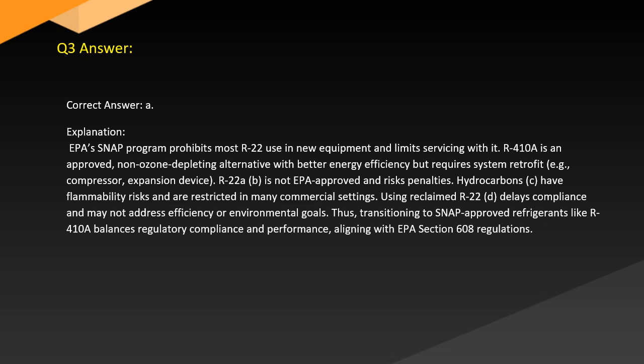Answer. Correct answer: A. Explanation. The EPA SNAP program prohibits most R22 use in new equipment and limits servicing with it. R-410A is an approved, non-ozone-depleting alternative with better energy efficiency but requires system retrofit, including the compressor and expansion device. R22A (B) is not EPA approved and risks penalties. Hydrocarbons (C) have flammability risks and are restricted in many commercial settings. Using reclaimed R22 (D) delays compliance and may not address efficiency or environmental goals. Thus, transitioning to SNAP-approved refrigerants like R-410A balances regulatory compliance and performance, aligning with EPA Section 608 regulations.